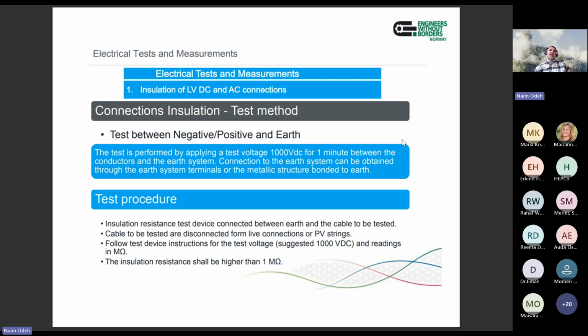If you have any leakage or any short anywhere in the circuit, you will have low ohm readings. That means there is a problem somewhere in the system, so you need to work on fixing this issue. If you get a number higher than 1 megaohm, that means everything is okay, and this string or this circuit is marked okay.